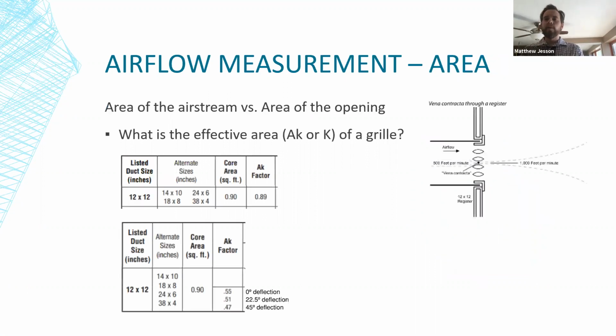The first part of that equation that we're going to talk about, area. If you're measuring airflow inside a duct, that area is really straightforward and easy to define. But when you're measuring face velocity at a grill or a register, that area becomes a more complicated question, because you need to look at the area of the airstream, not just the area of the grill itself. On the right, you can see the diagram of the airflow coming through your vena contracta as it comes through the blades of the grill, and then it spreads out as it gets out of the grill.